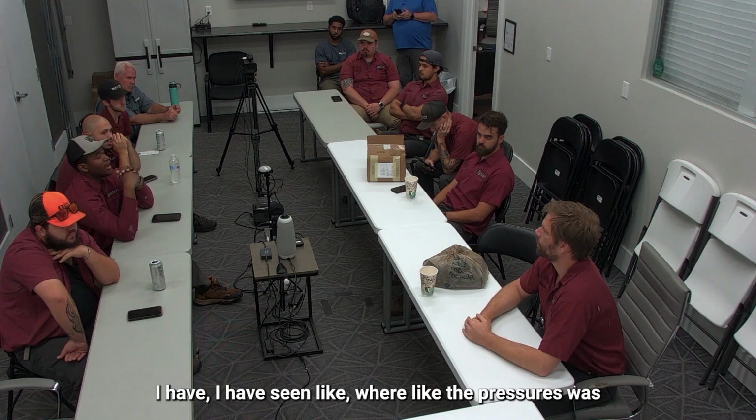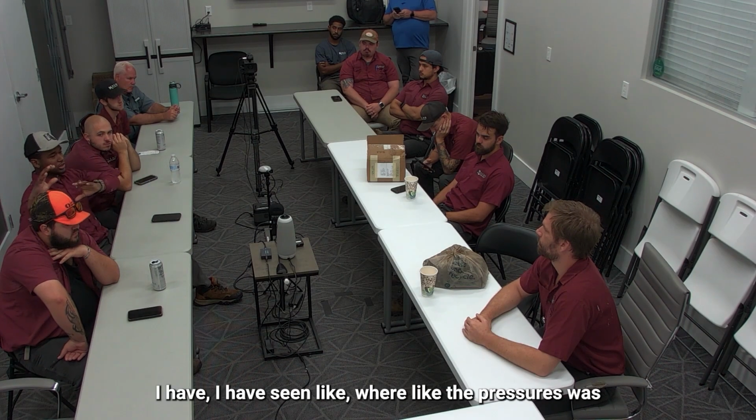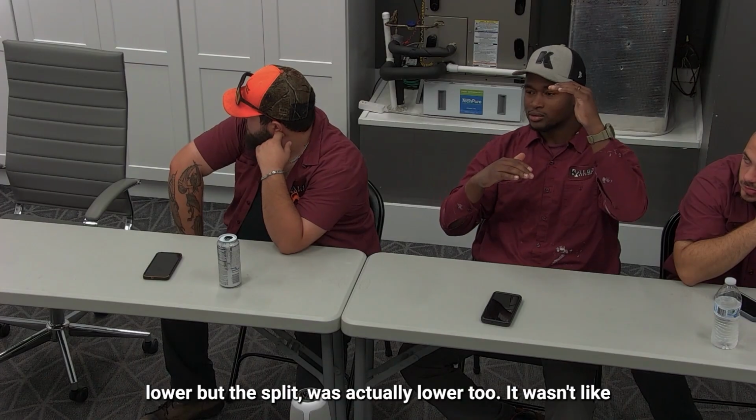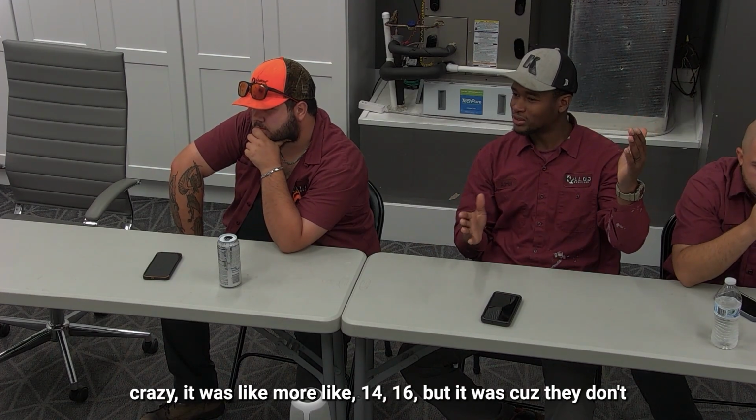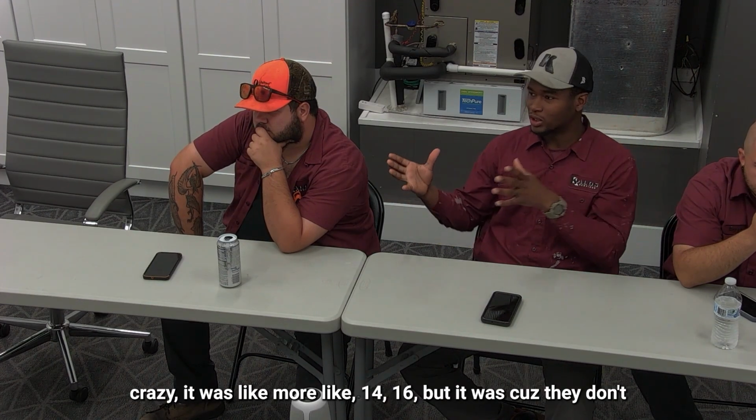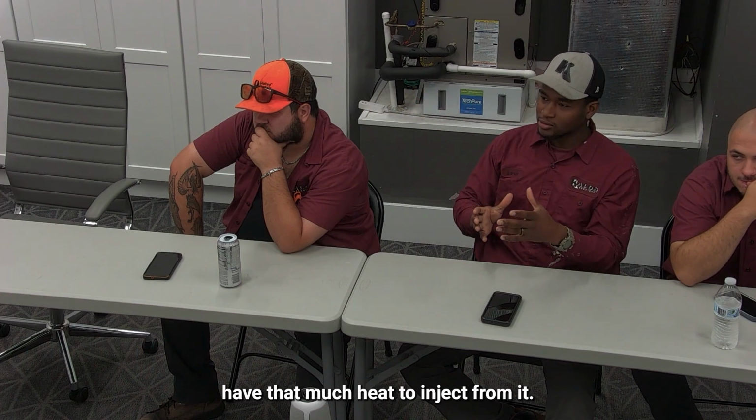Okay, so that's a good question. Actually, cold house can be a little bit tricky on the split. The cold house situation that I brought up is not really related to the split as much as it's understanding that we have less of a heat load, so we have lower refrigerant pressures. I have seen where the pressures were lower, but the split was actually lower too. It wasn't crazy, it was more like 14, 16, but it was because they don't have that much heat to inject from it.